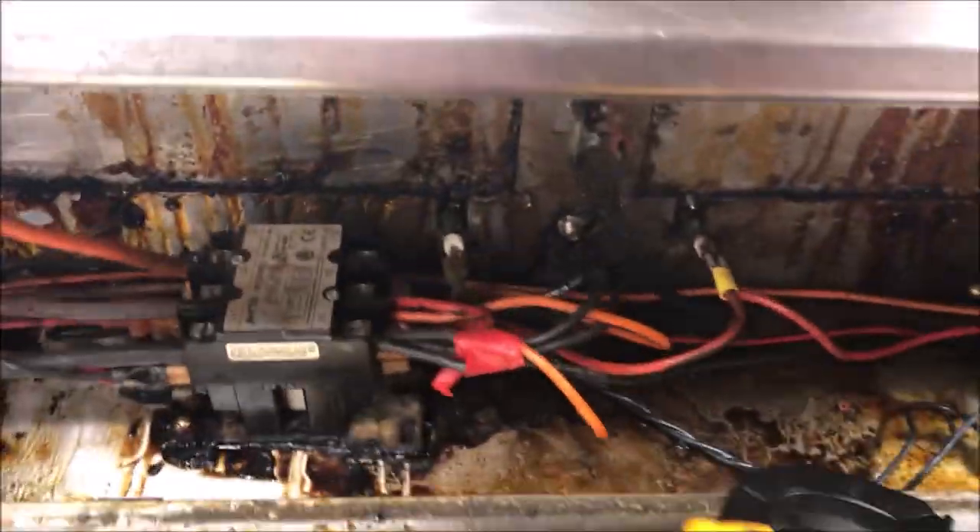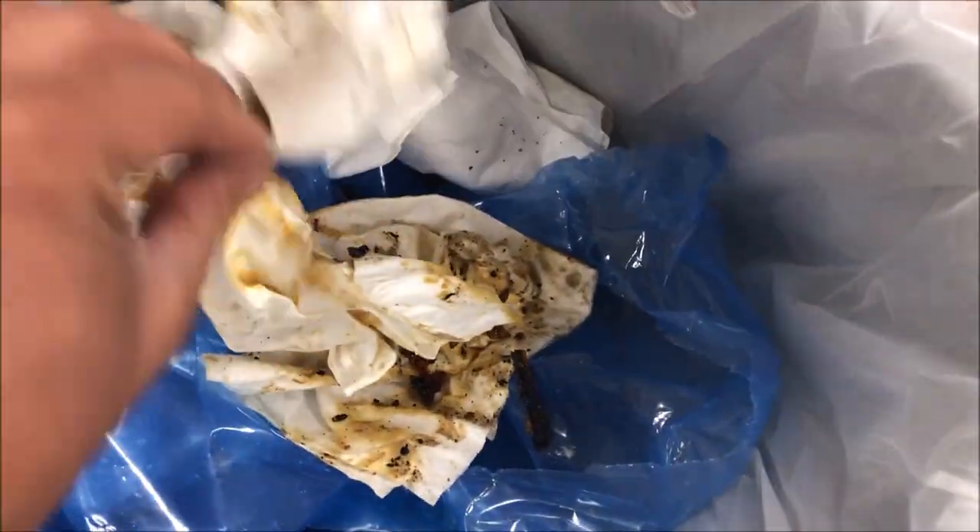Hello everyone. Today I'm working on a Henny Penny HMR-107 hot case. What's happening is we're blowing the breaker as soon as we turn it on. We had tons of grease in there - I cleaned out what I could as best as I could. It's really sticky stuff. Most of the wiring is still covered in the grease.